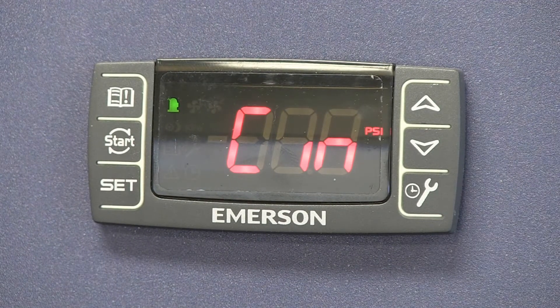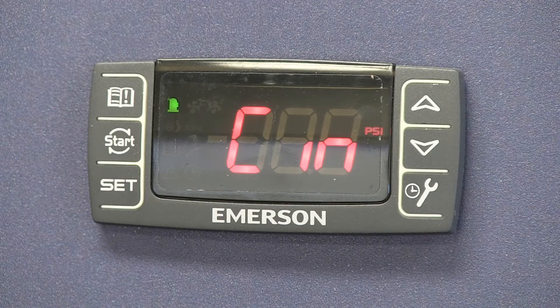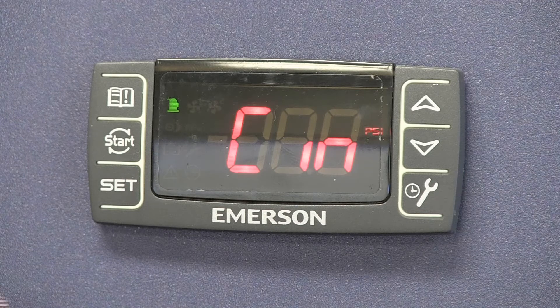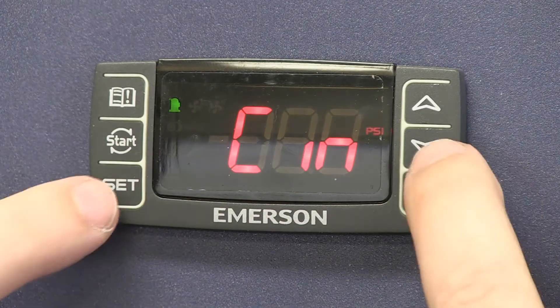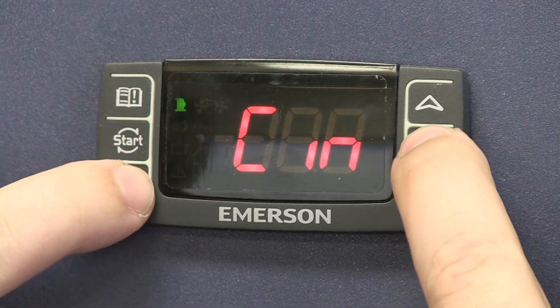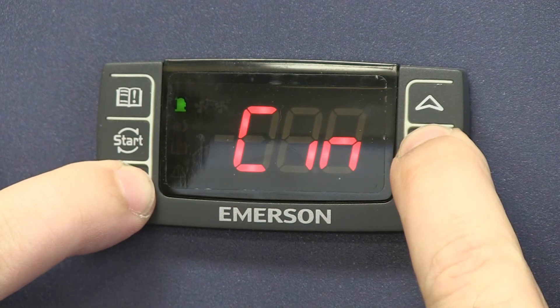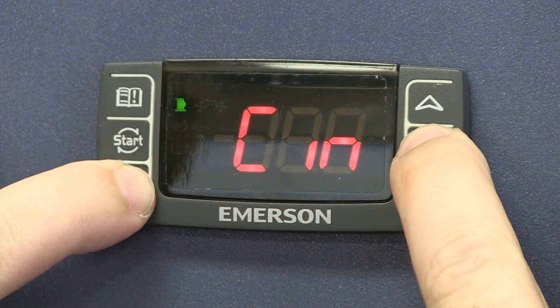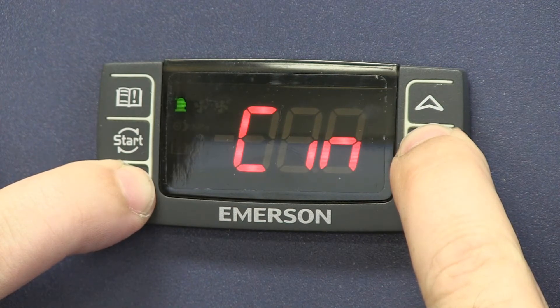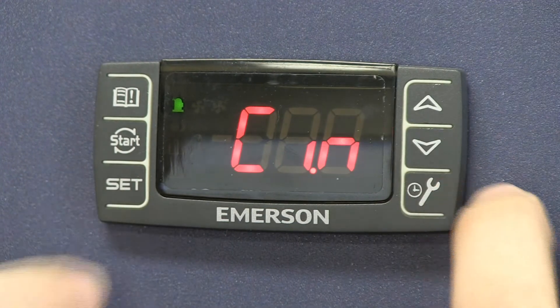However, to get to the fan controls, we actually have to get to the second level. So to do that, we hold the set and the down arrow key again for a few more seconds, about seven seconds, and it'll get into the level two menu.